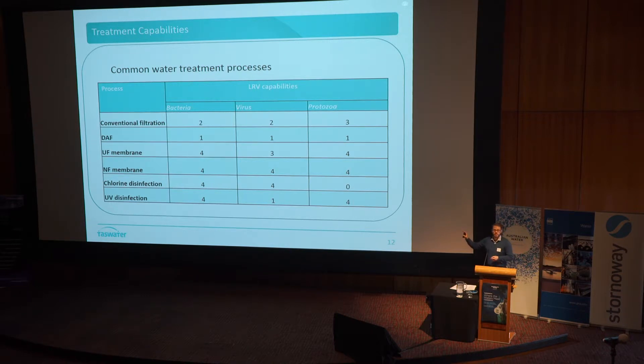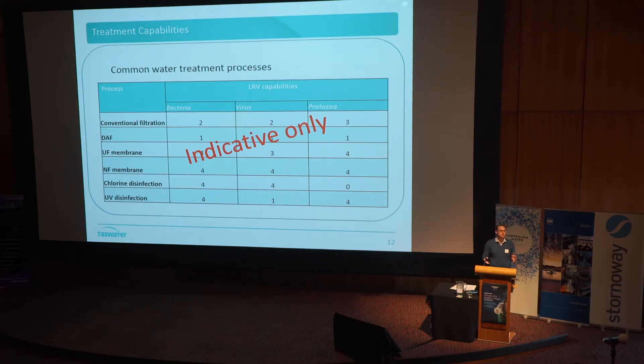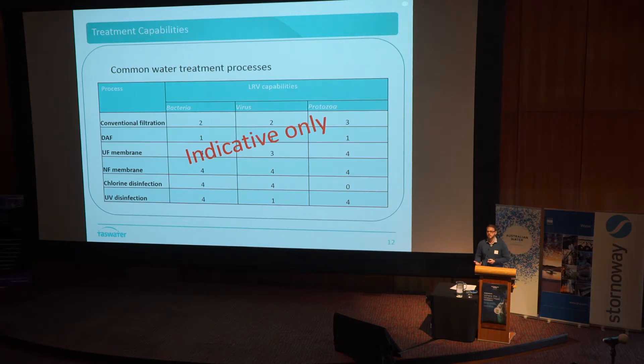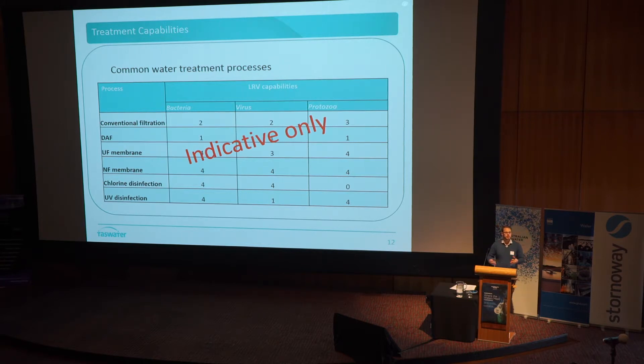I hate this slide — I put it up every time and I hate it because people take it as gospel. These numbers are indicative of what different treatment processes can do. We have a multi-barrier approach because different treatment processes are good at doing certain things and reducing different types of bugs. A good example is chlorine disinfection: chlorine is really good at killing viruses and bacteria, but it's rubbish at killing protozoa — so if you swim, just watch out. UV disinfection is kind of the opposite: really good at inactivating protozoa and bacteria, but not so good with viruses. That's why we use multiple treatment barriers along a train to get to our water quality objectives.